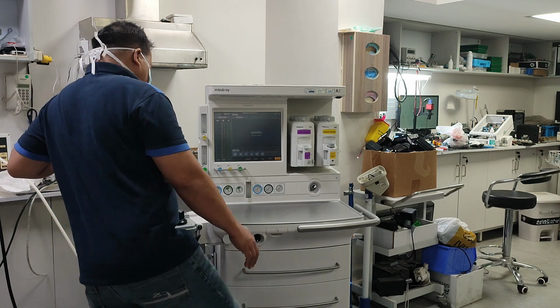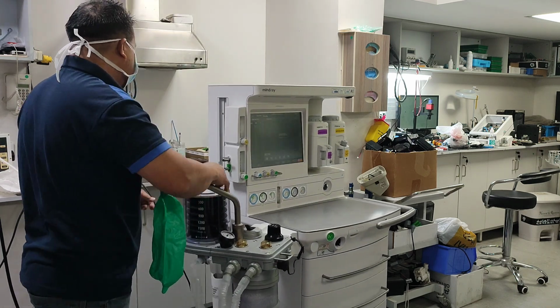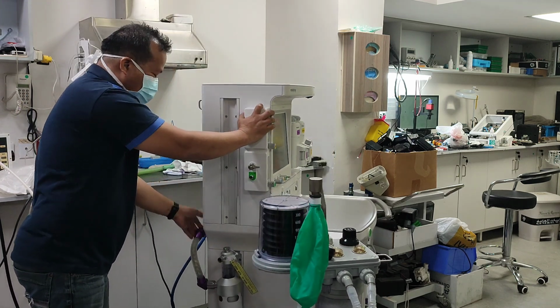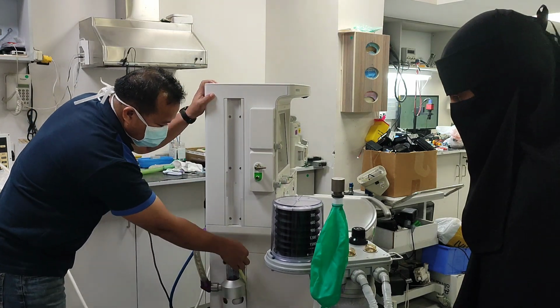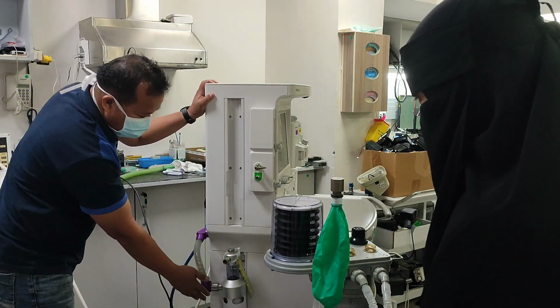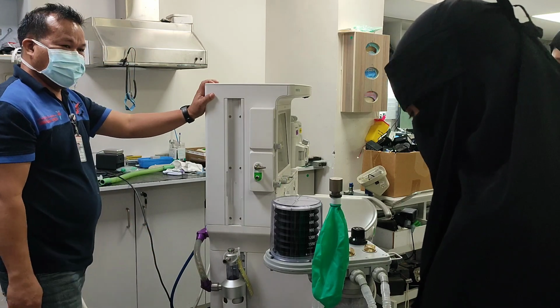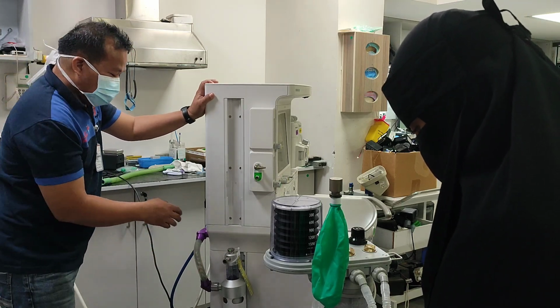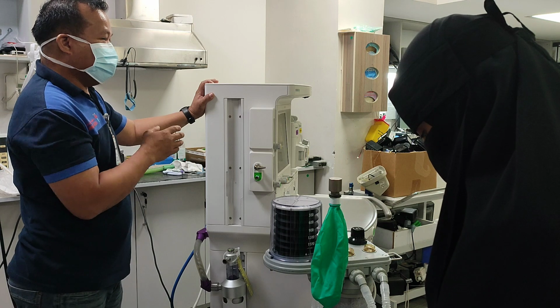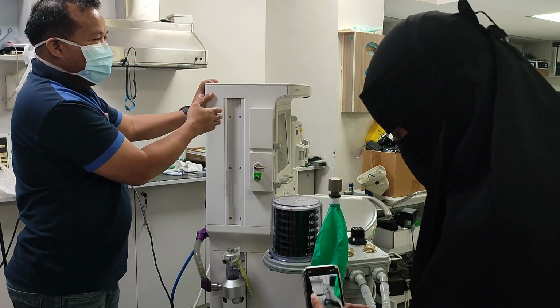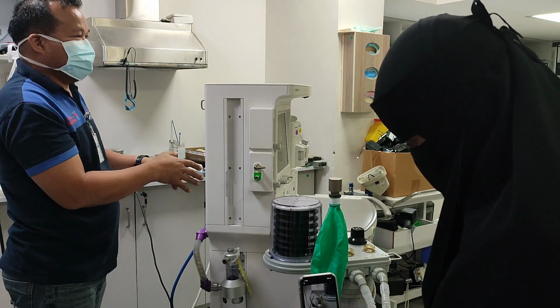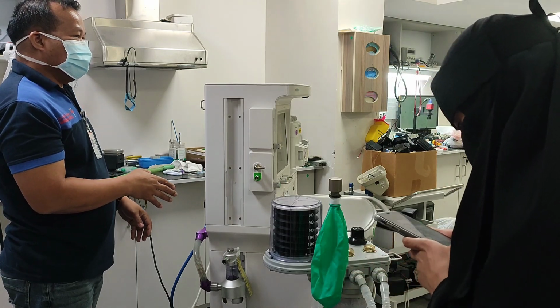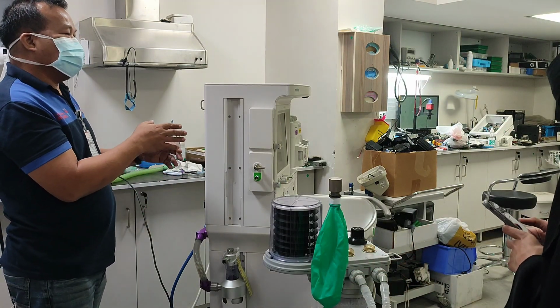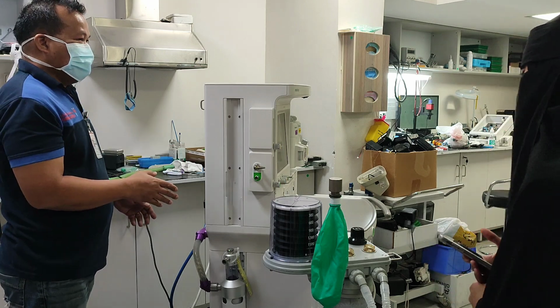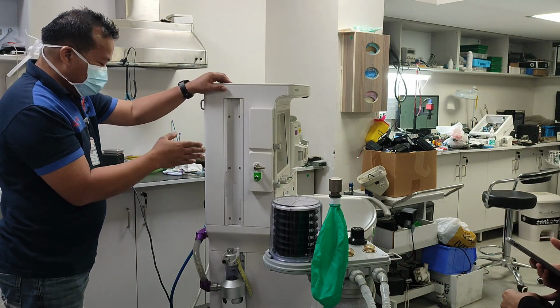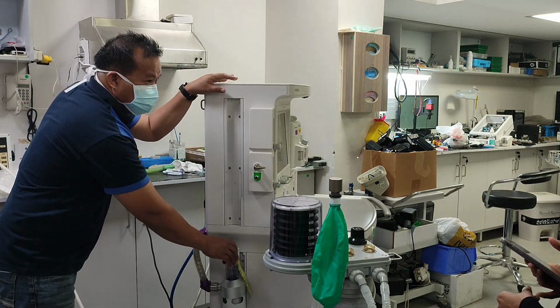So here, this is important also. If you see here, we have a tank here. So what is the use of this one? This is for the scavenging system. During the operation, they are using the gases. So if there is excess gas, where will it go? It will not be inhaled by the user or the others. So for this machine, they are putting a scavenging system.